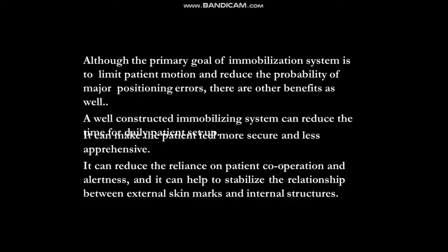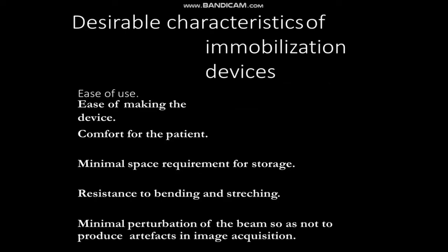Although the primary goal of an immobilization system is to limit patient motion and reduce the probability of major positioning errors, there are other benefits as well. A well-constructed immobilizing system can reduce the time for daily patient setup. It can reduce the reliance on patient cooperation and alertness, and it can help to stabilize the relationship between external skin marks and internal structures.